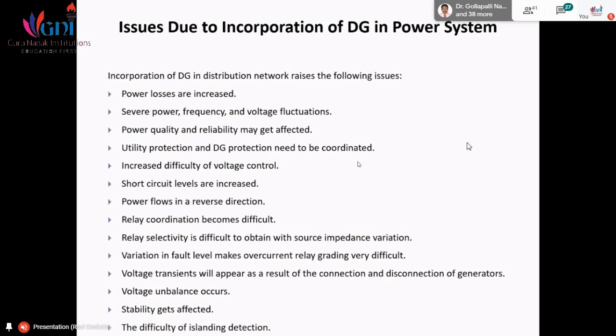Then next is stability gets affected. Whenever you connect the DG to the system, stability is important, because if some parameters are fluctuating, that will disobey the rule of synchronization, and then your DG will not work properly in the utility or grid.